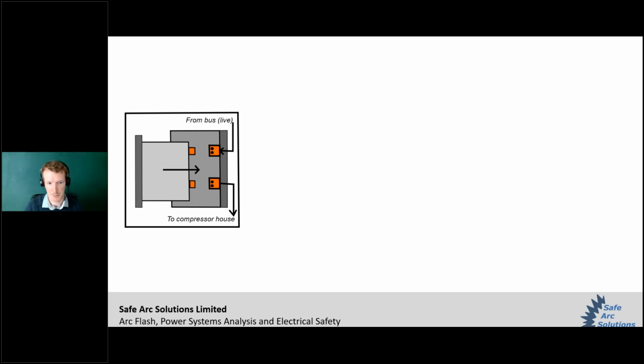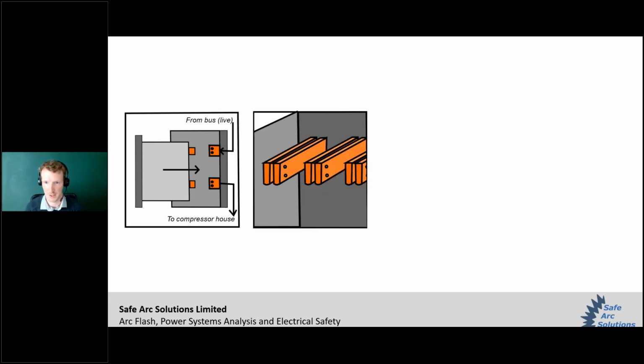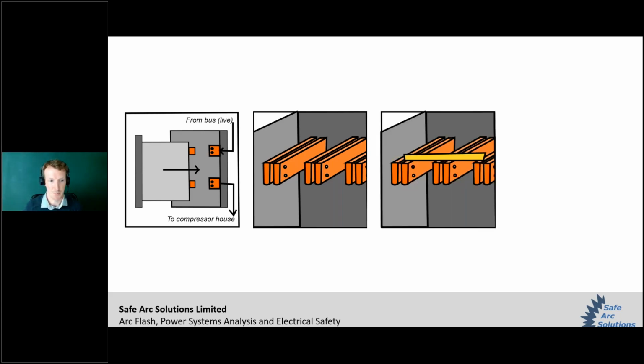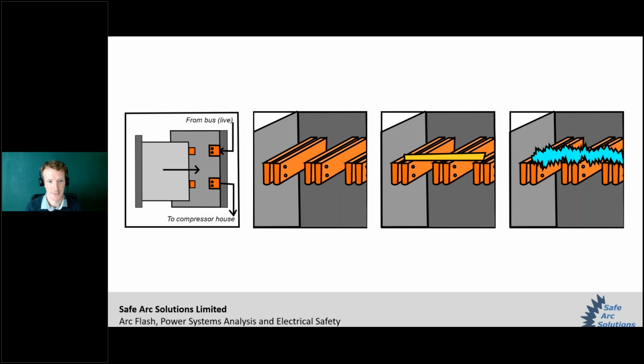As the breaker was being racked in, somewhere in the mechanism, a metal piece that had come loose during maintenance broke off, and it pinged across these copper conducting bars at the back of the panel, which are, as I say, alive. It briefly bridged the gap between these three conducting phases, and this is what sets off the arc flash. A very high current flows through the metal piece, acting as a short effectively between those conducting parts.